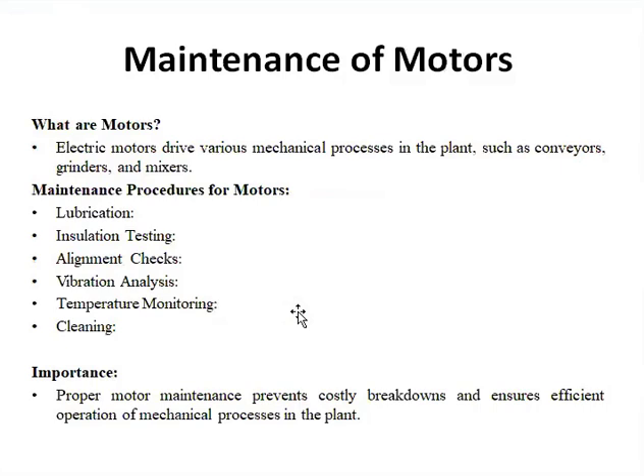As for maintenance of motors, I also do maintenance of motors. Electric motors drive various mechanical processes in the plant, such as conveyors, grinders, and mixers. So a motor is a very big component in our factory. It does almost everything, so its functionality is crucial in production. If it is working properly, it increases the production output. We produce a lot of products, so we always ought to make it work efficiently. We normally check on lubrication, insulation, alignment checks, vibration analysis, temperature monitoring, and cleaning.